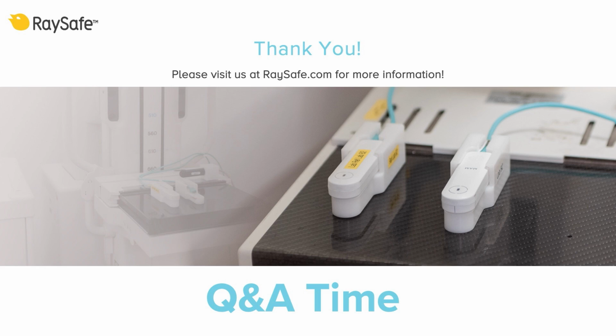One can also see it as a service to the user, because if we have fewer calibration points, the actual calibration process goes faster. But I can say that we are currently looking into expanding the calibration of the 452 with more dose rates. It's not decided when to implement it, but we are looking into it at least.